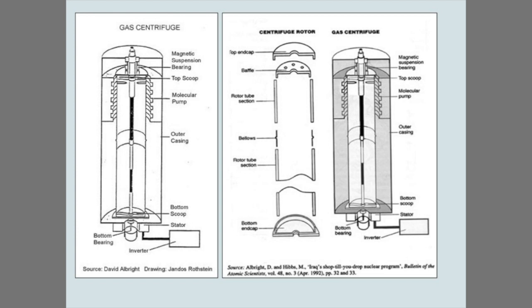There's a magnetic suspension at the top, and the bottom suspension is generally a needle bearing. You see that operating in the picture on the left. It's sitting on a needle that is inside some ball bearings, and there's an electric motor or inverter that powers the centrifuge. It causes the rotor to spin.